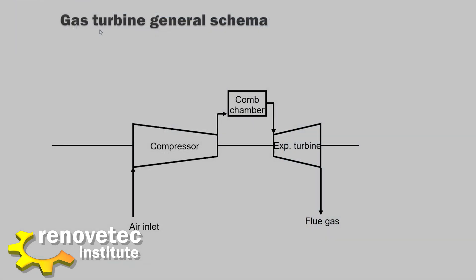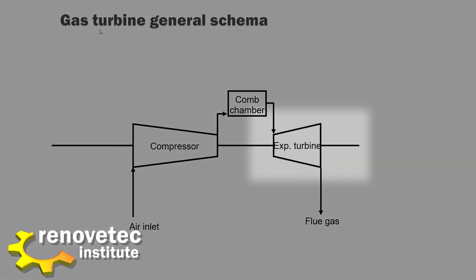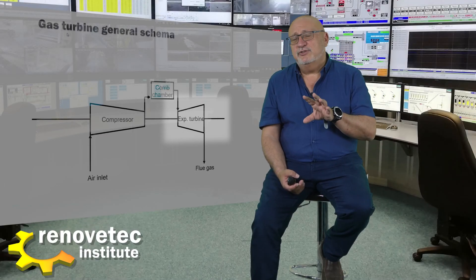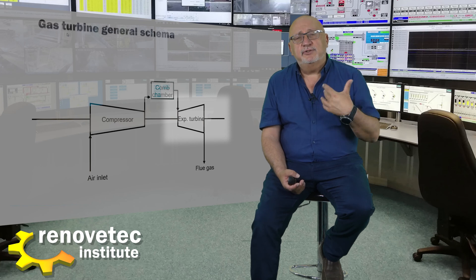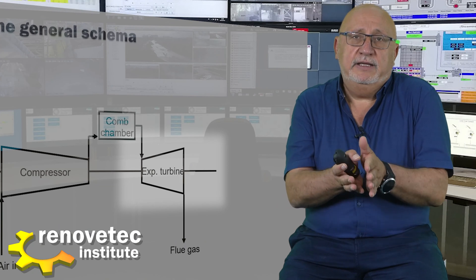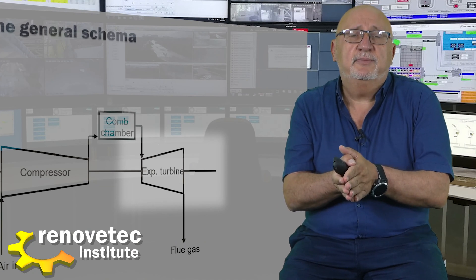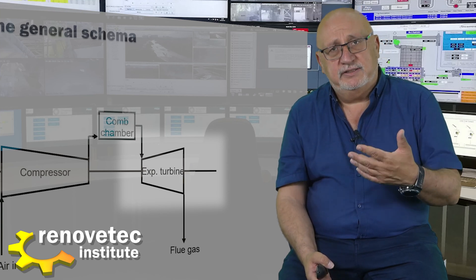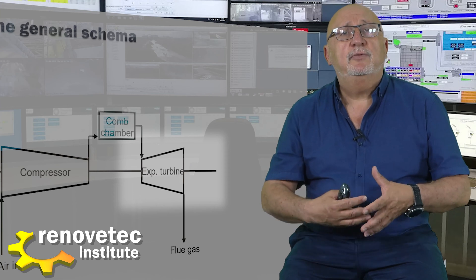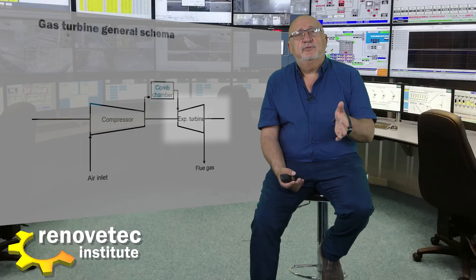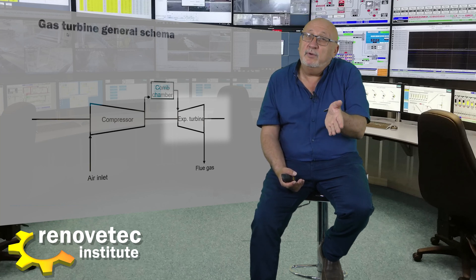The third element is the expansion turbine. Remember that in the compressor we increase the pressure, in the combustion chamber we increase the temperature of the air, and now at the outlet of the combustion chamber we have air that is both heated and pressurized. In the expansion turbine, we release this pressure. The most normal inlet temperature is around 1200, 1300, or even 1400 degrees.